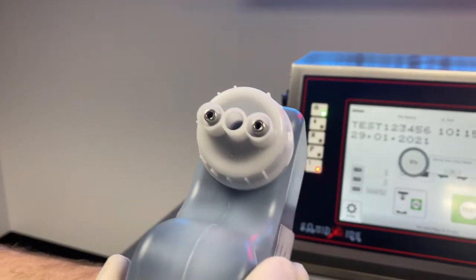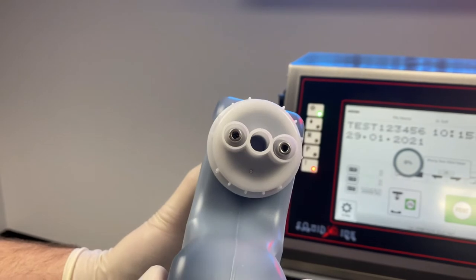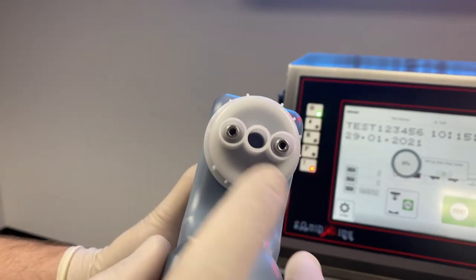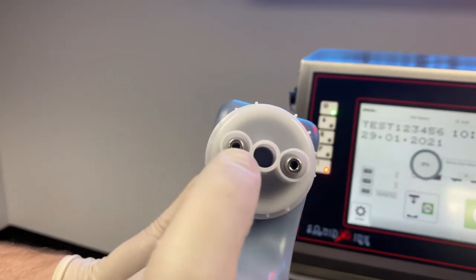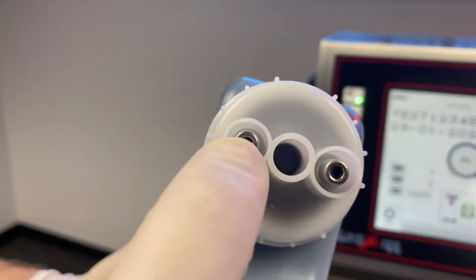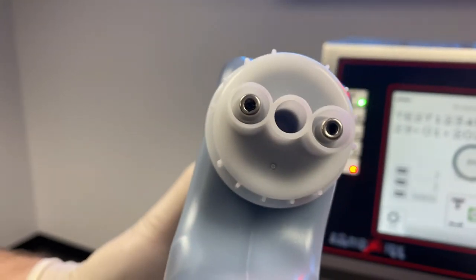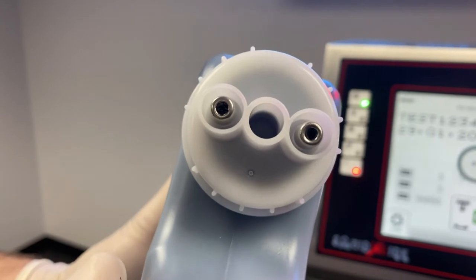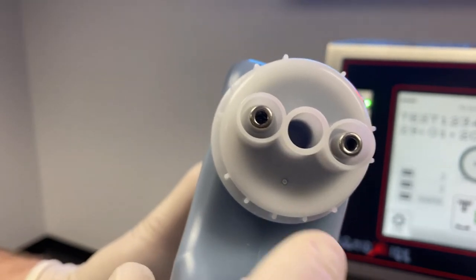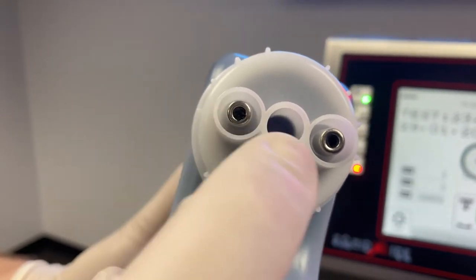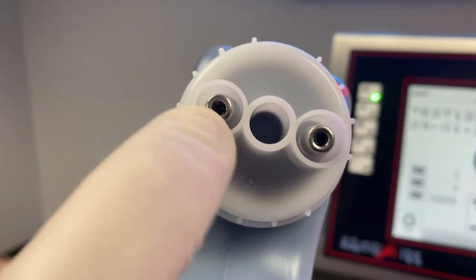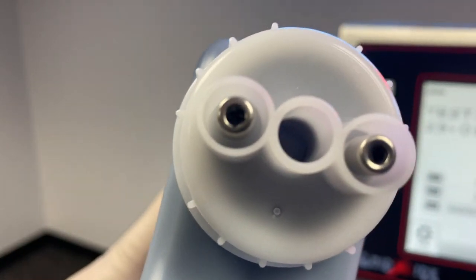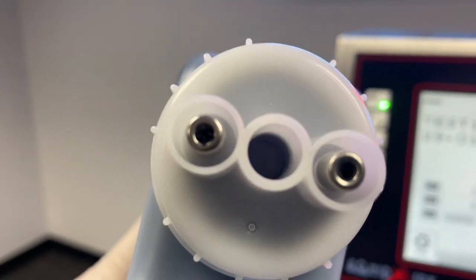Another good visual indicator for the cartridge as to whether or not things are okay here is you'll see we have two membranes that get punctured when we slide the cartridge in. One is for fluid out, one is for air displacement. You should fairly clearly be able to see that these are punctured to allow both fluid and air to flow.